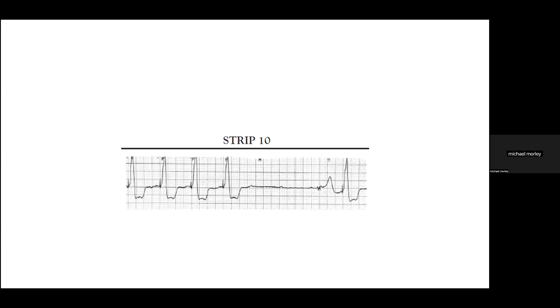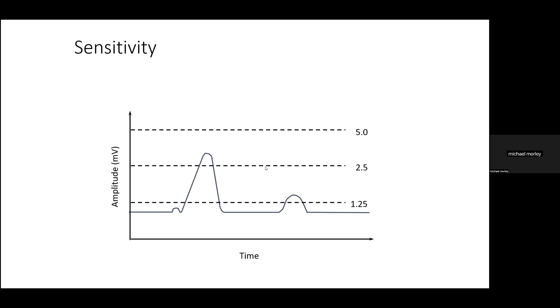So that brings us on to sensitivity. So the pacemaker can see electrical activity that's passing by the tip of the lead. What it doesn't know is what these impulses are. And so we use changes in sensitivity to make the device more sensitive or less sensitive to ensure that we can get the pacemaker to see and respond to and take notice of what we want it to take notice of, i.e. the ventricular activity, whilst ignoring noise, background noise, electrical interference, far field signals from other chambers, or sensing of the T waves. And so our top left-hand knob on our temporary pacing box allows us to make the pacemaker system more sensitive or less sensitive, depending on which way we turn the knob.